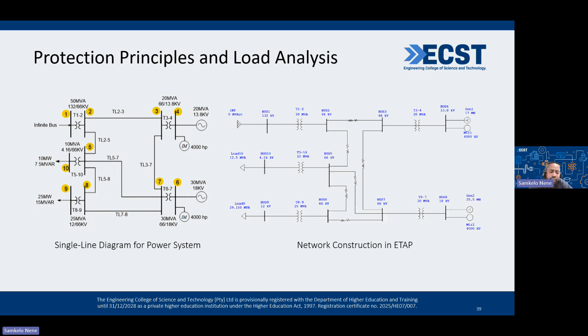One of the important things as well is the protection of the system. This is like the basics of protection. You'll find that the system has protection zones - there'll be protection for the generator, protection for the transmission lines. The protection zone acts like a primary protection; they have to detect whatever fault within them. If they don't, then a backup protection zone, which is a secondary protection, will then react.